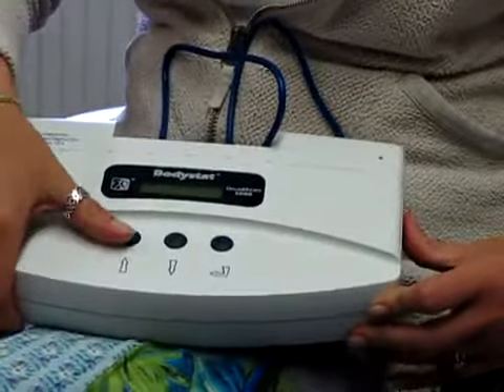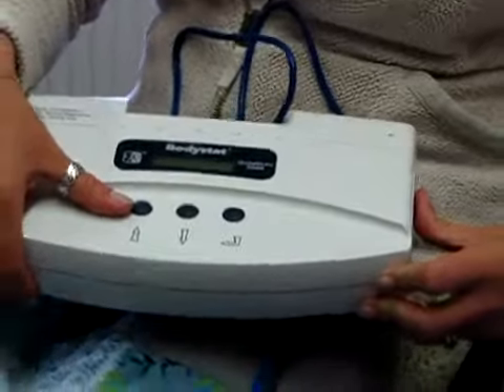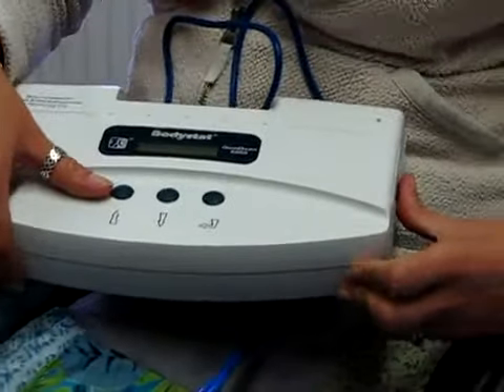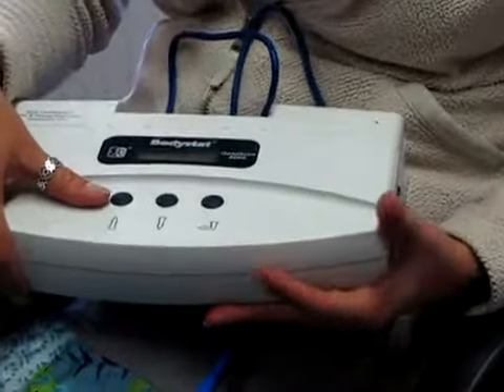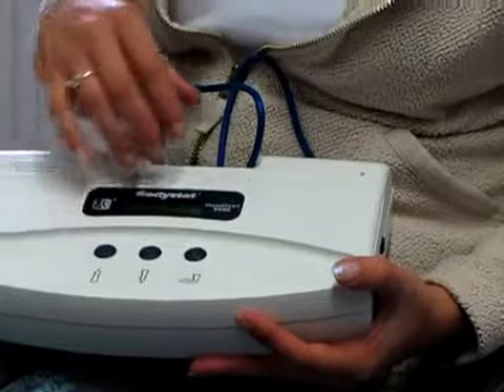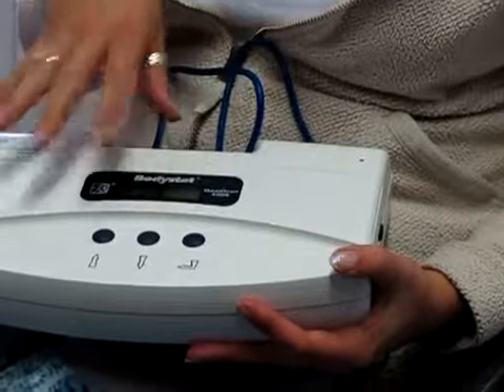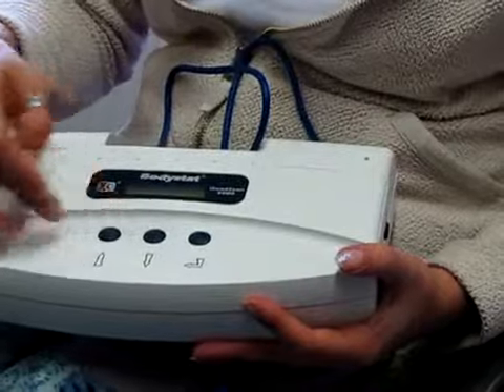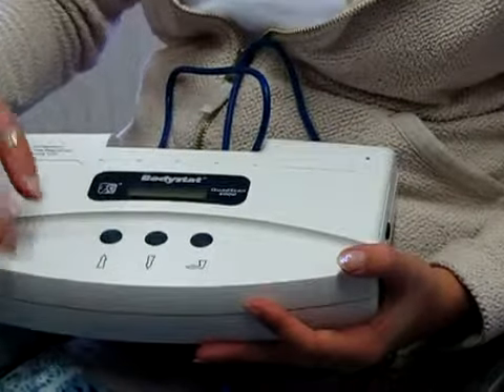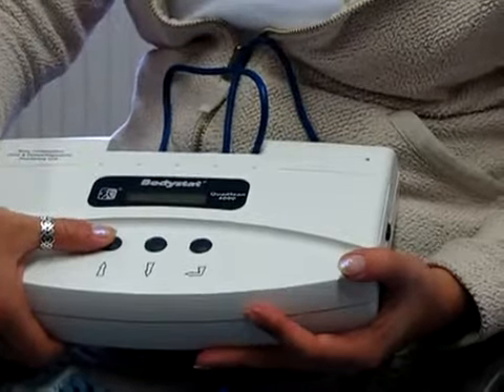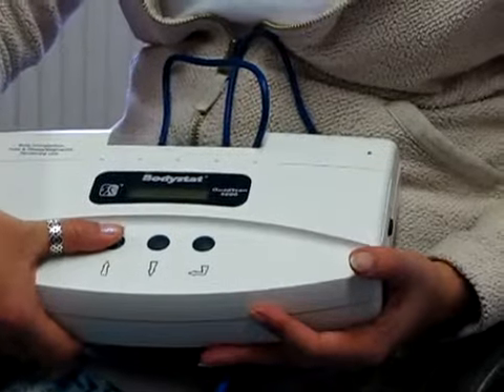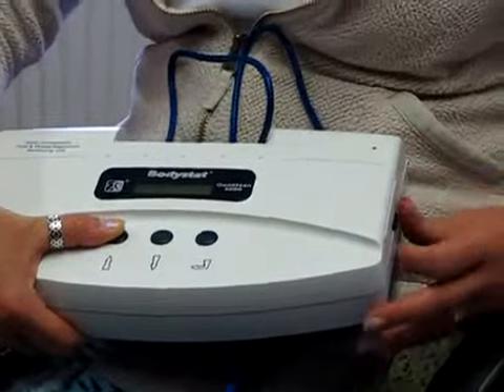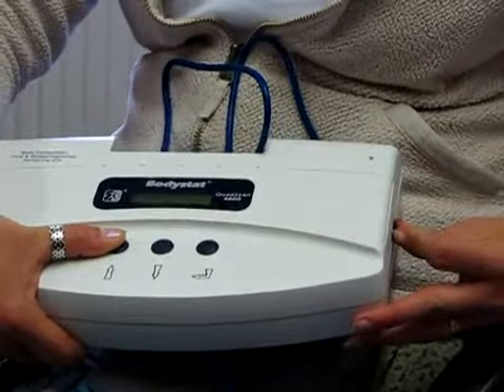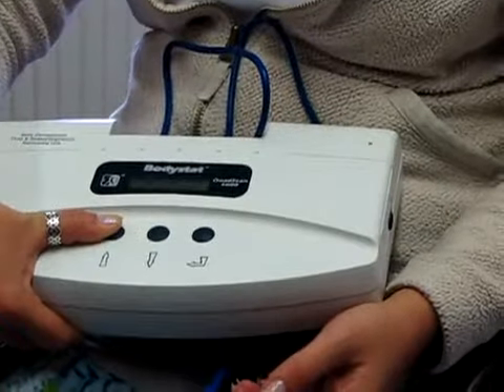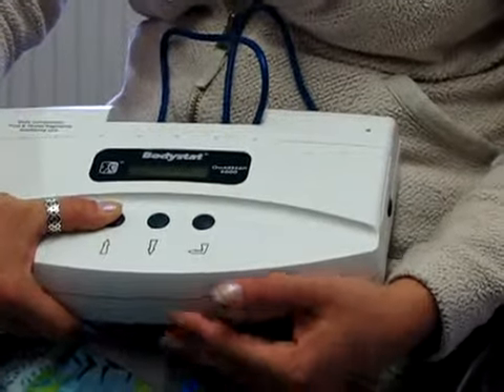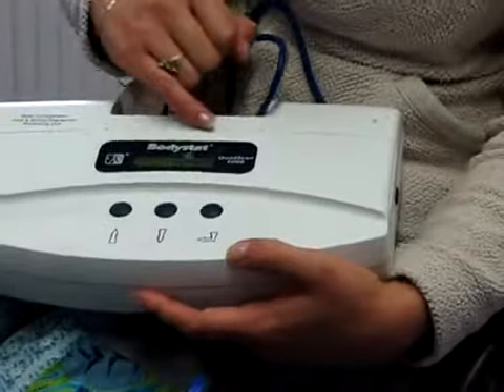You can go into the installation mode if you wish to alter any of those parameters, or if you are using this device for research and you want to use it in a different fashion, you can change all the parameters inside by using the installation mode. Simply to go into installation mode, you just press the up arrow key, keep your finger on that whilst you switch the device on. You get the welcome screen again, and then it comes up with installation mode.